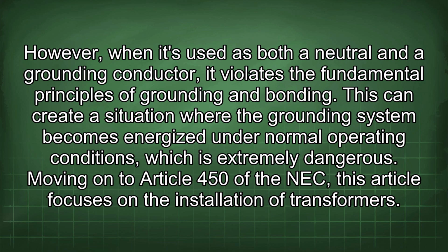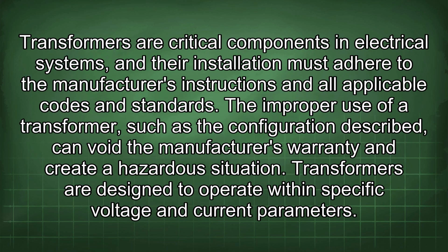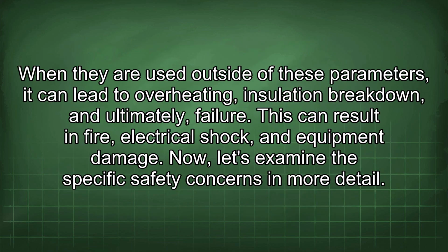Moving on to Article 450 of the NEC, this article focuses on the installation of transformers. Transformers are critical components in electrical systems, and their installation must adhere to the manufacturer's instructions and all applicable codes and standards. The improper use of a transformer, such as the configuration described, can void the manufacturer's warranty and create a hazardous situation. Transformers are designed to operate within specific voltage and current parameters. When they are used outside of these parameters, it can lead to overheating, insulation breakdown, and ultimately failure. This can result in fire, electrical shock, and equipment damage.